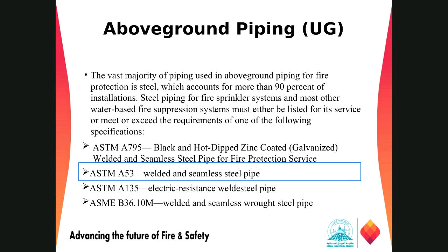So steel piping for a water-based fire sprinkler system must be listed for its service or exceed the requirement of one of the following. Listed does not mean listed by UL or FM. They are talking about the piping manufacturer as per those requirements, ASTM A53 or ASTM A135 or all those requirements. All right. Normally for above ground piping, we are using in most of the cases ASTM A53 for our applications.